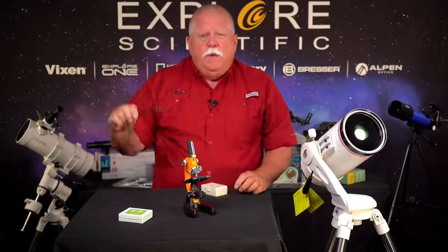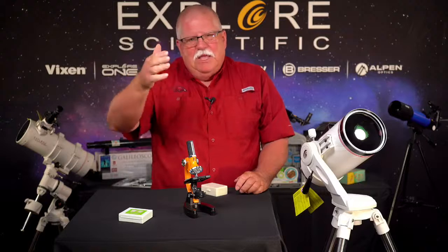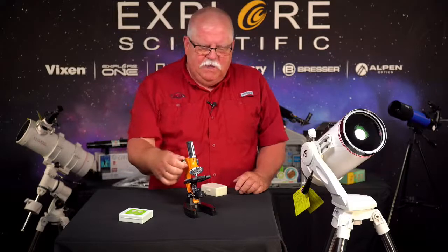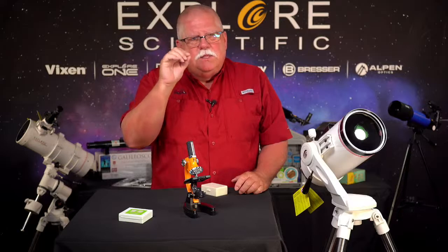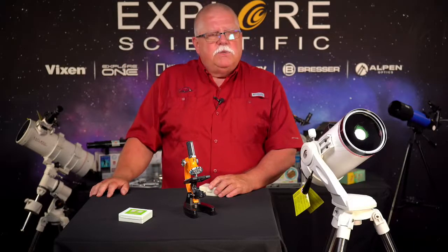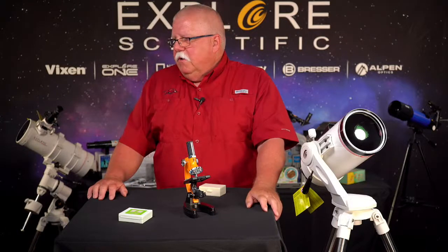I think people, or I know people, try to focus way too fast. They expect it to come into focus like a camera and then go out. Really long focus. That's not the way a microscope works, because what you're focusing on is so thin and so tiny and so small, the depth of field, which is the term that describes how big the focus is where it's in focus, is, no pun intended, microscopic, because it's just fractions of a millimeter.